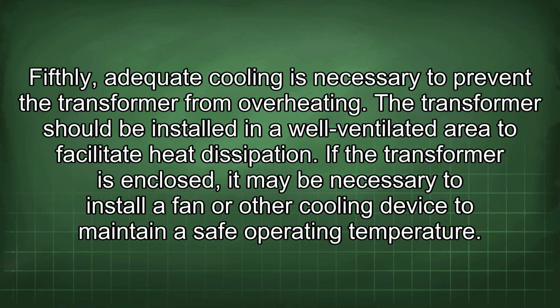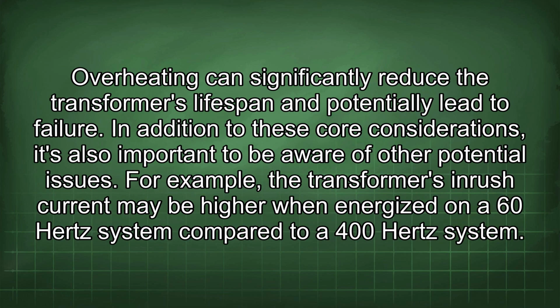Fifthly, adequate cooling is necessary to prevent the transformer from overheating. The transformer should be installed in a well-ventilated area to facilitate heat dissipation. If the transformer is enclosed, it may be necessary to install a fan or other cooling device to maintain a safe operating temperature. Overheating can significantly reduce the transformer's lifespan and potentially lead to failure.